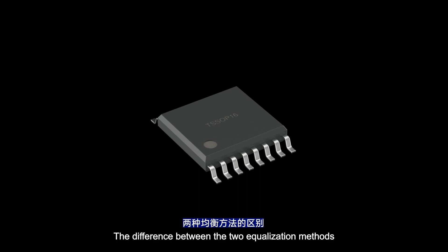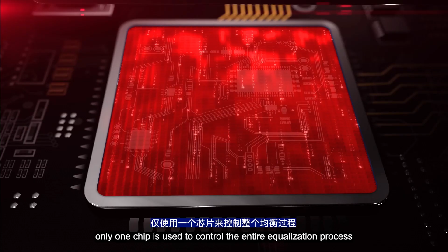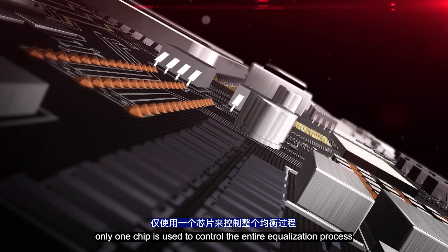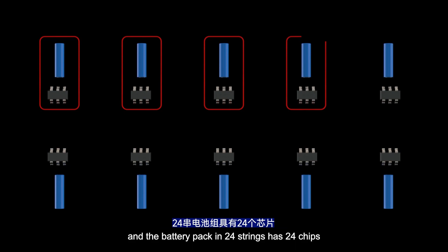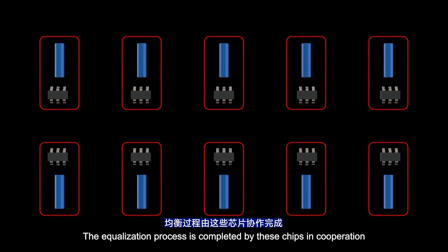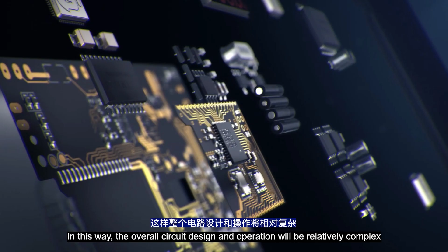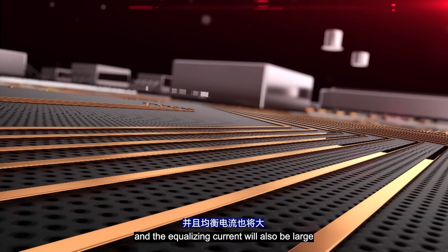The difference between the two equalization methods is that the capacitive type is relatively simple. Only one chip is used to control the entire equalization process, and the equalization current is also small. The inductive type has one chip in each string, so a battery pack with 24 strings has 24 chips. The equalization process is completed by these chips working together. This makes the overall circuit design and operation relatively complex, and the equalizing current will also be large.